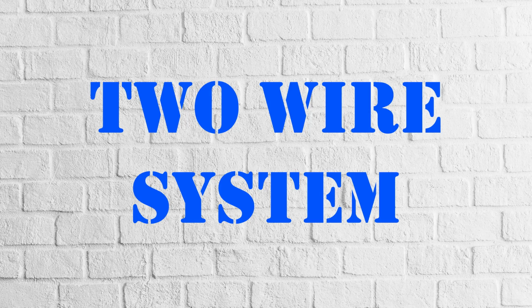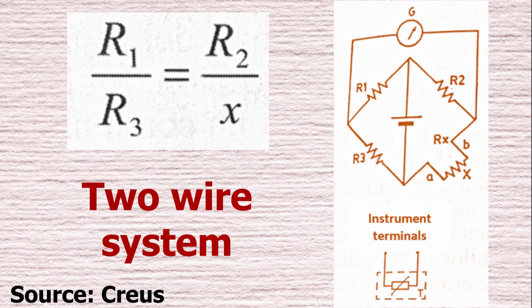The Wheatstone bridge is arranged in 2, 3, or 4 wire systems, depending on the connection wires of the bridge resistance probe. In the 2-wire system, the resistance probe is connected to one of the arms of the bridge, and R3 is varied until the galvanometer deviation is cancelled. At that time, this equation is fulfilled, and from here, X is deduced as the value of the resistance probe.